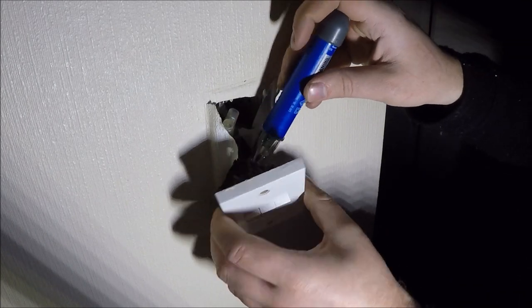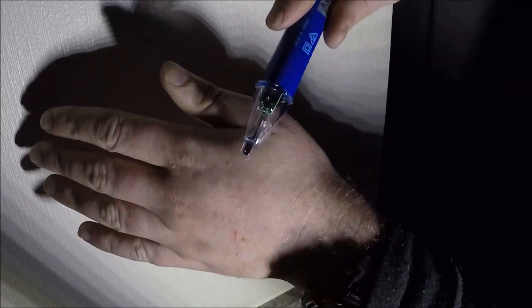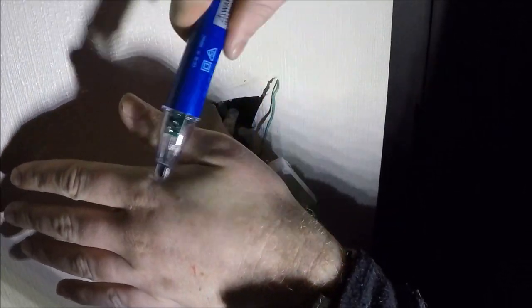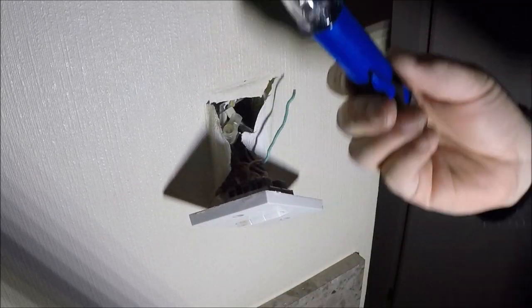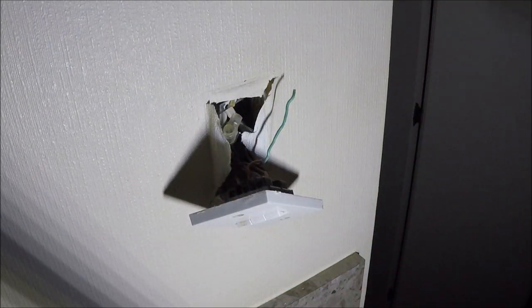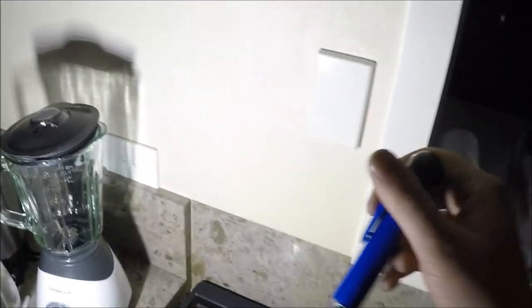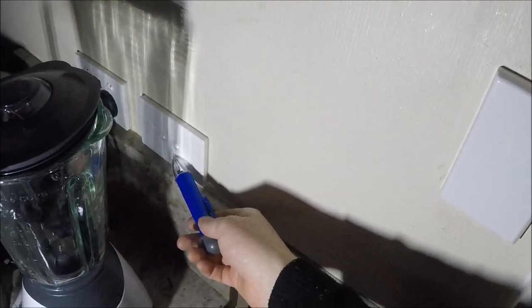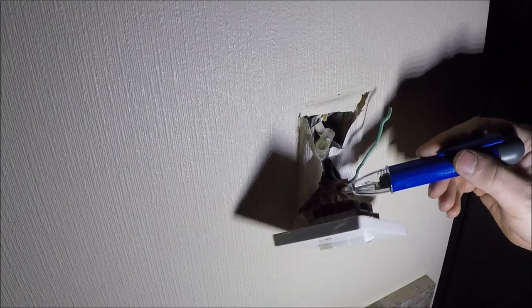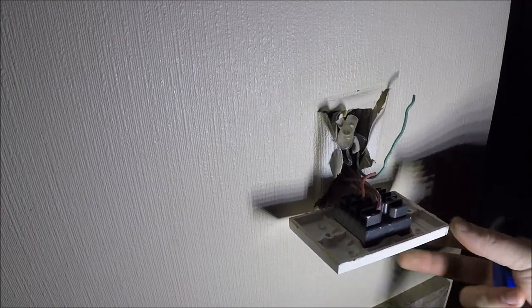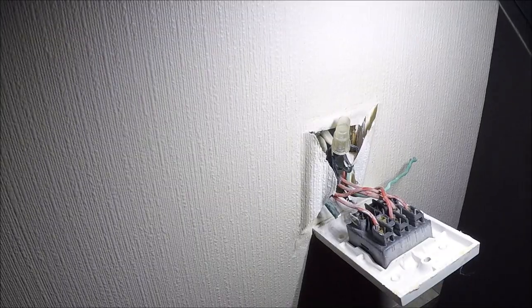Obviously it's not picking up any voltage. If it does, it's just voltage from moving it around. But everything's dead there. Always test that these work on a live outlet. So what I've done, gone over to where the other light is and made sure that this is working. So always double check to ensure. If you really want to, test with your multimeter.